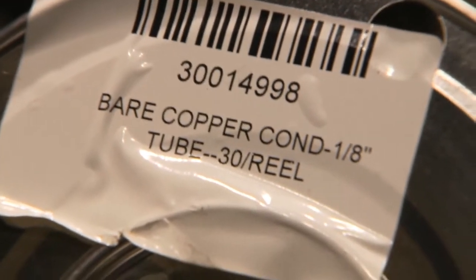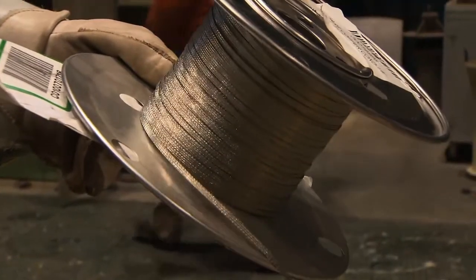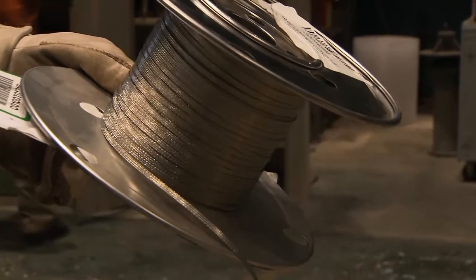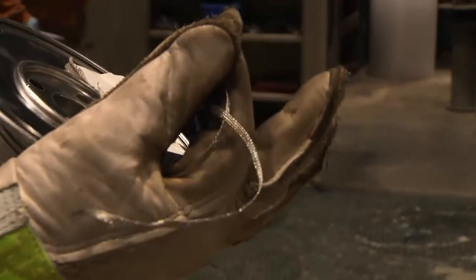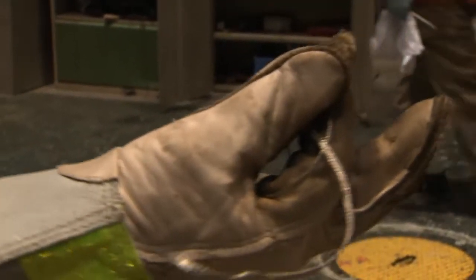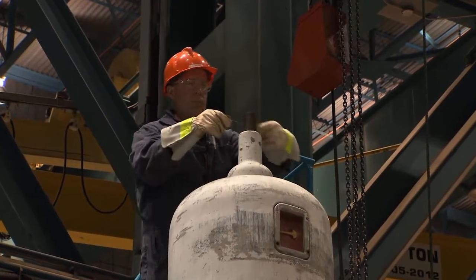After the Megger test is complete and indicates that the bushing is still in very good condition, additional electrical tests, commonly called the Doble C1 and C2 insulation tests, are performed in order to determine the integrity of the main insulation and the tap insulation within the bushing.